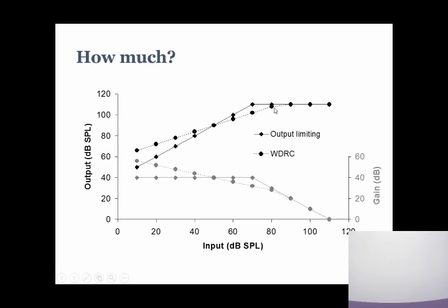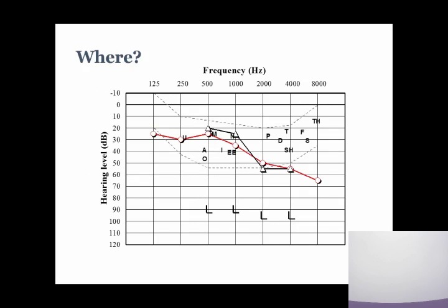This is like an older hearing aid effectively. Newer hearing aids would rather do a WDRC, wide dynamic range compression, which means we do it, we'll talk about that in a second, in bands. And in each band we have a much steeper curve, and then the lower threshold, and then we have actually a linear, and then a compensation at the top. So we've got no gain anymore.